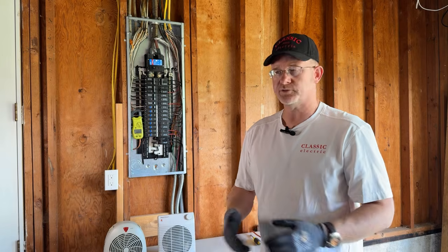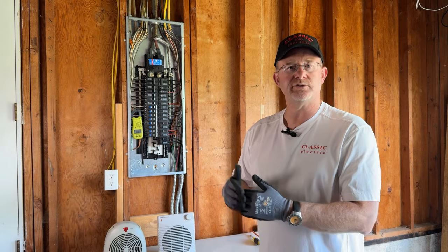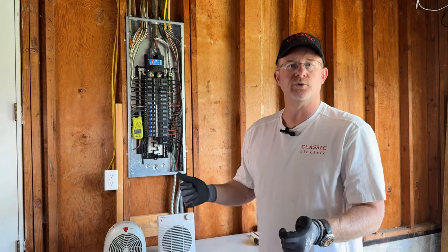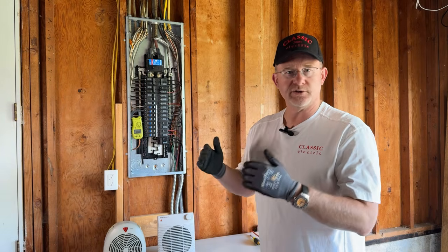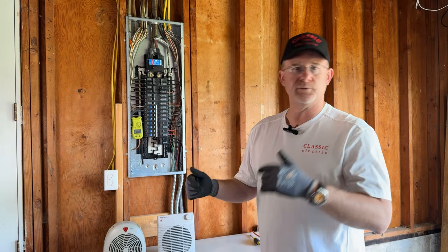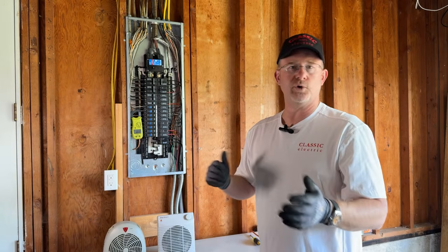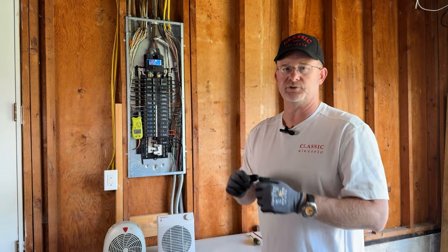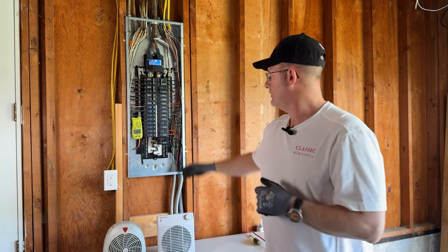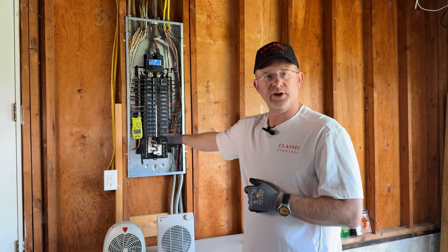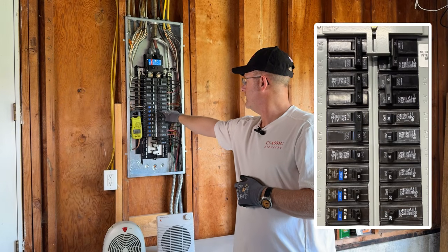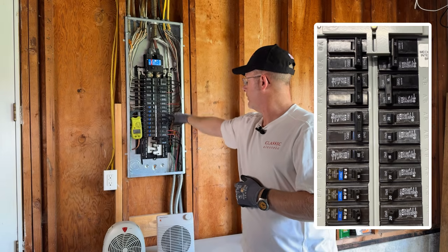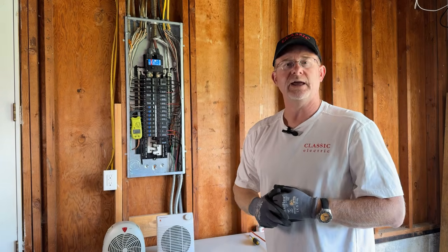So what am I talking about? I got a 15 amp breaker and it's got 16, 17, 18 amps and the breaker opens. Or I got a 20 amp circuit, which is what we're going to test right here. And it's going to get to 21, 22, 23, depending on whether it's really cold outside or it's a warm day. I mean, it's going to have a little fluctuation, but basically it's going to trip right where the indicator of the numbers are on the breaker. Like this one here is 15, 15, 15, 15. I got 20, I got 30, I got 40. That's what that's representing is amps.